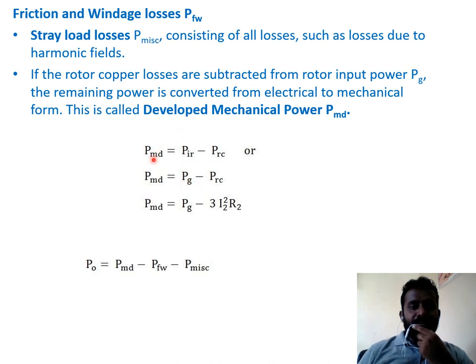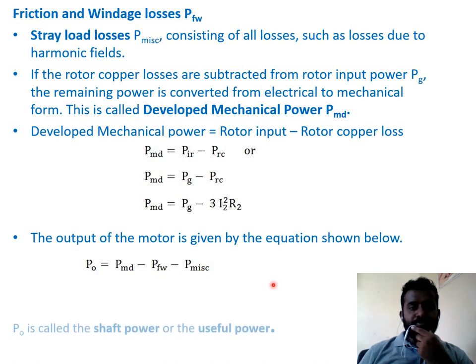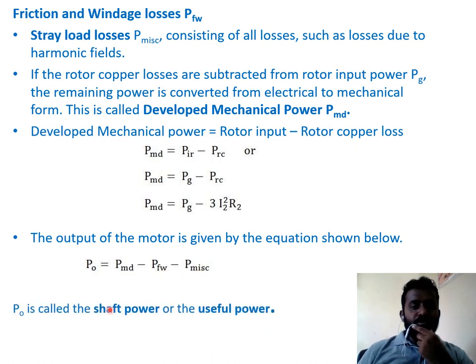The mechanical power developed is equal to PG minus 3 × I₂² × R2. Mechanical power developed equals rotor input minus rotor copper losses. The total power output of the motor Po equals the mechanical power developed minus friction, windage, and miscellaneous stray losses. P output is the shaft power, the useful power out of the rotor of the machine.